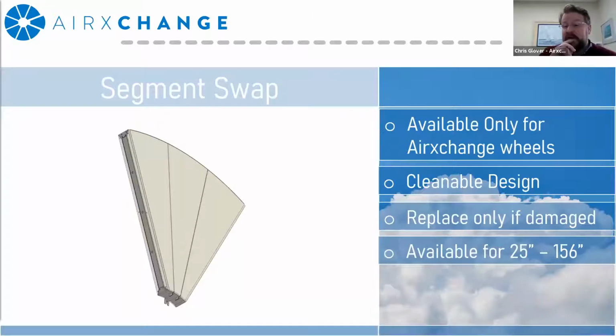So there are times where you may need to replace them. That could be if it was subject to mechanical damage. Maybe someone went up to service the unit and accidentally put a hammer through something. Or if it's just at an age where it's time to replace them with a new set due to some deterioration of the material over time. A typical segment swap out usually takes about 20 to 30 minutes for damaged segments. And once again, because it's segmented in nature, if you are replacing a damaged segment, you don't necessarily have to replace the entire wheel. You can look at just replacing that singular piece to help save your customer cost with the device itself. The segments themselves range from 25 inches all the way up to 156 inches.